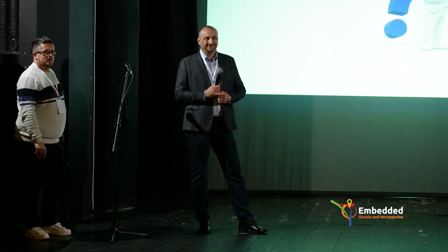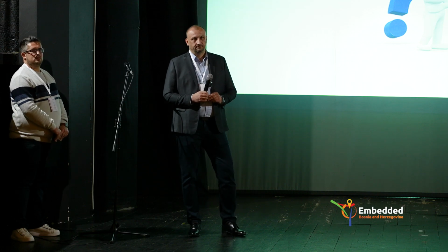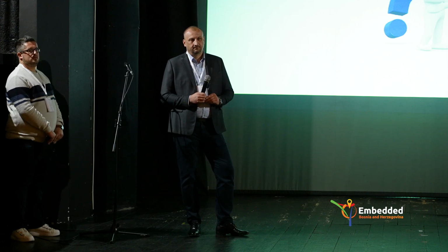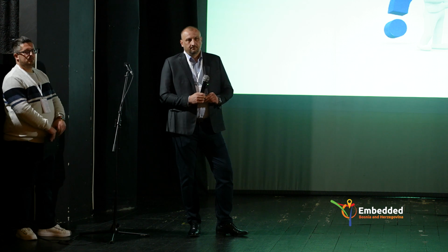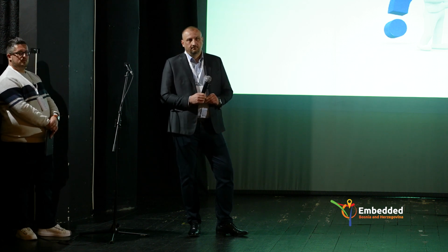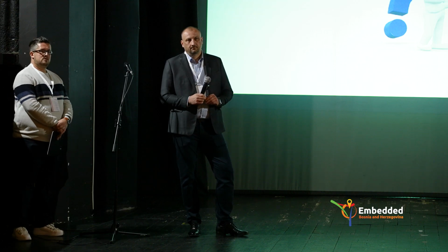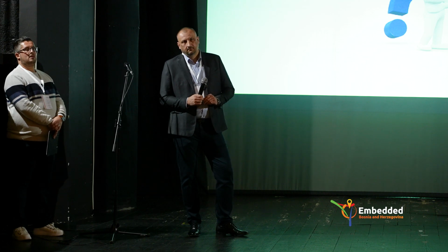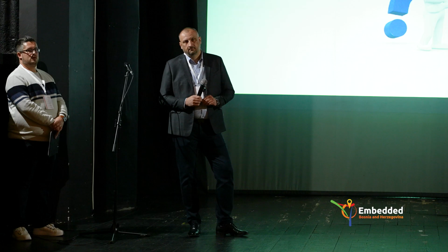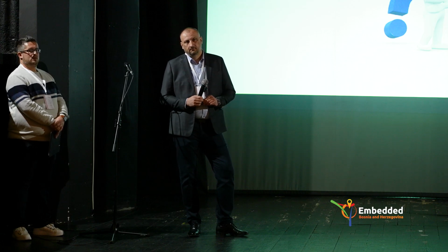Hello. So I have one question. When we have a medical device, we do the risk assessment, risk management, and basically we do assessment of the hardware, in this case on one project that I worked on. So everything that can go wrong. For example, if we have one chip, and the possibility for the voltage on that chip to go above the maximum value is under the limits of that chip, so this is the normal condition. But do we need to test and verify that, or can we argue that this cannot happen, so that we don't need to conduct any test which can damage the chip, if you understand what I mean?